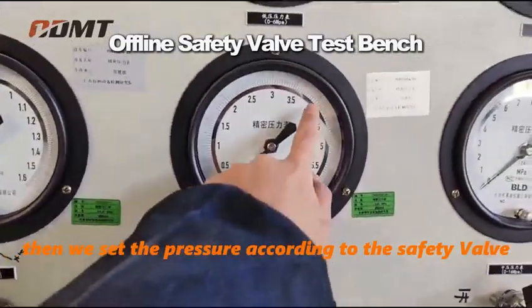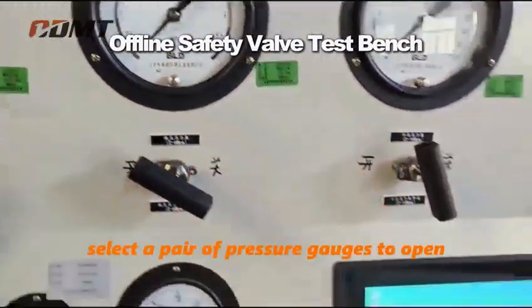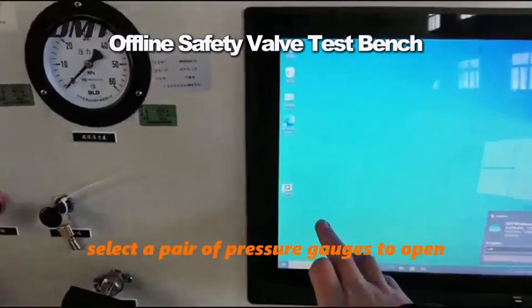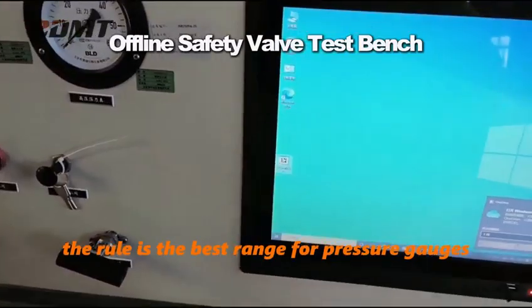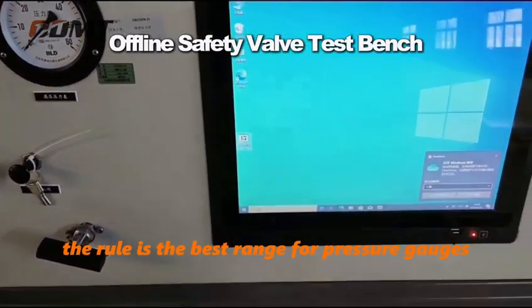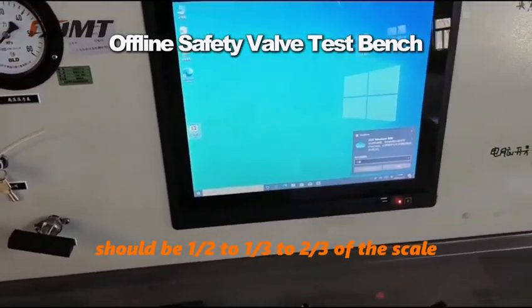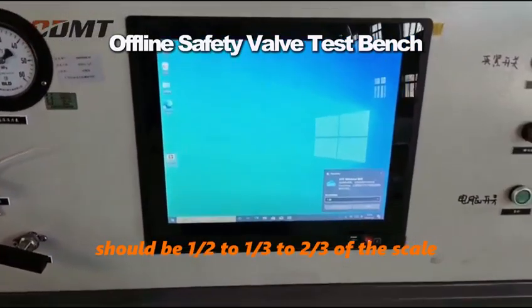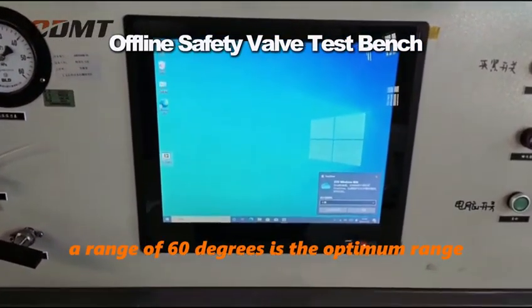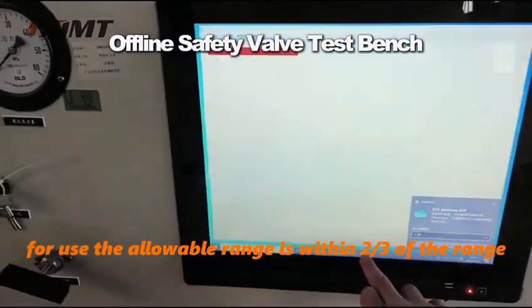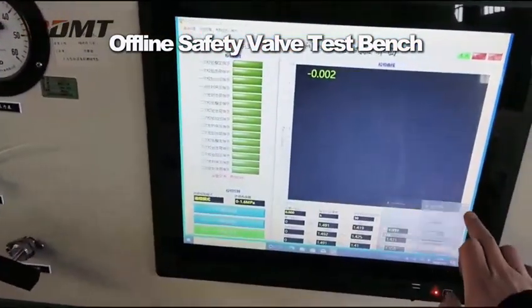Then we set the pressure according to the safety valve. Select a pressure gauge to open. The rule for selecting the pressure gauge is that the best range should be 1/3 to 2/3 of the scale. That's about it. A range of 60 degrees is the optimum range for use. The allowable range is within 3/4 of the range.